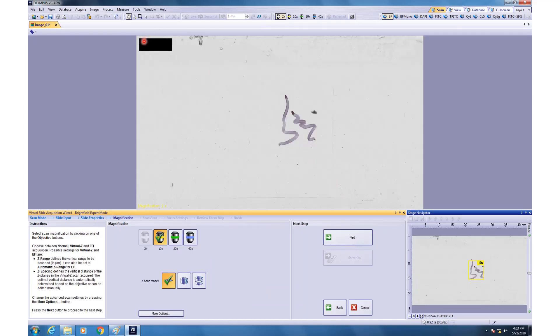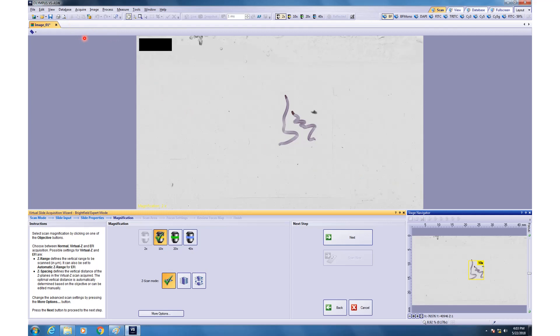The microscope will automatically take a 2x image, go back and forth, back and forth and create this large scale image. If you feel that all the object has not been covered in this area, say suppose there is something which is left over here, you can actually click this button here, it is inactive right now but in previous slide it was active. So, you can go back and click this and then it will ask you go to the top corner, left corner and go to the right bottom corner and it will again acquire the overview image.